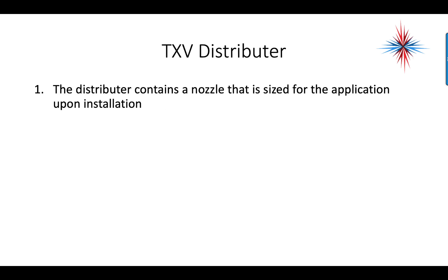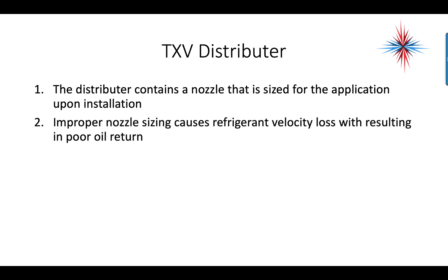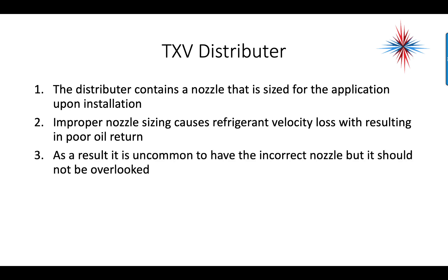TXV distributors can cause problems as well. The distributor contains a nozzle that is sized for the application upon installation. Improper nozzle sizing causes refrigerant velocity loss that results in poor oil return. It's uncommon to have the incorrect nozzle, but it should not be overlooked.